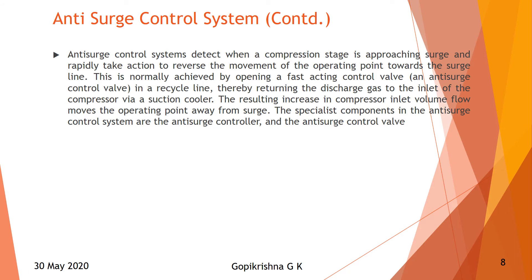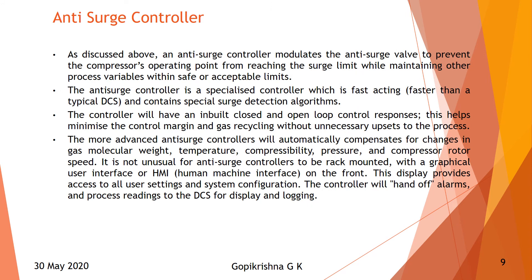The anti-surge controller modulates the anti-surge valve to prevent the compressor operating point from reaching the surge limit while maintaining other process variables within safe or acceptable limits. The anti-surge controller is a specialized, fast-acting controller with special surge detection algorithms. It has inbuilt closed and open loop control responses, which help minimize the control margin and recycling without unnecessary upset in the process. More advanced anti-surge controllers automatically compensate for changes in gas molecular weight, temperature, compressibility, pressure, and compressor rotor speed.